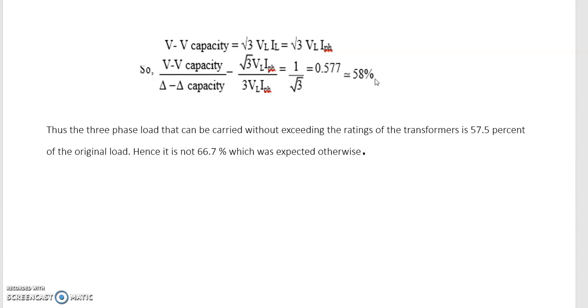Now if one of the transformers is removed from the bank, each transformer remaining is able to carry its rated full load current. Thus, removal of one transformer from bank reduces the full load line current from root three I to I amperes. Thus the capacity becomes 57.7 percent.